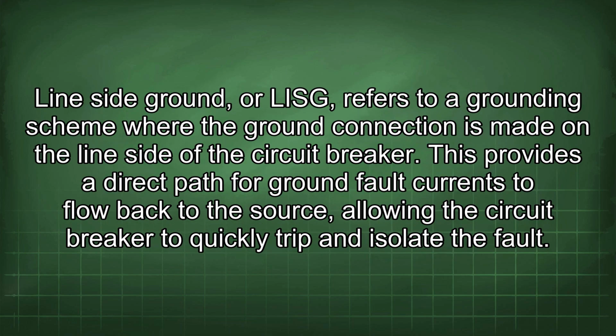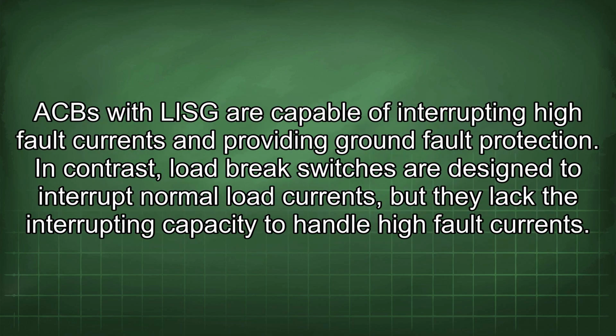Line-side ground, or LISG, refers to a grounding scheme where the ground connection is made on the line side of the circuit breaker. This provides a direct path for ground fault currents to flow back to the source, allowing the circuit breaker to quickly trip and isolate the fault. ACBs with LISG are capable of interrupting high fault currents and providing ground fault protection.